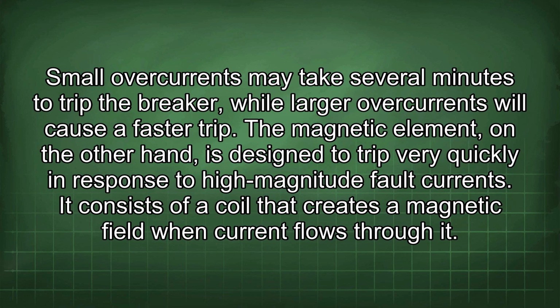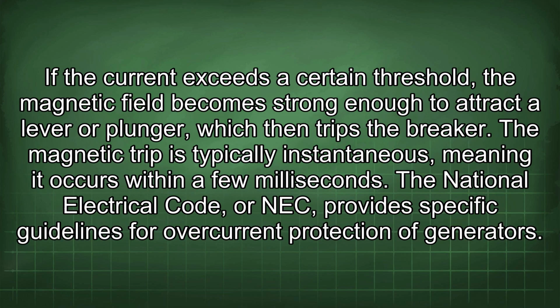The magnetic element, on the other hand, is designed to trip very quickly in response to high magnitude fault currents. It consists of a coil that creates a magnetic field when current flows through it. If the current exceeds a certain threshold, the magnetic field becomes strong enough to attract a lever or plunger, which then trips the breaker. The magnetic trip is typically instantaneous, meaning it occurs within a few milliseconds.